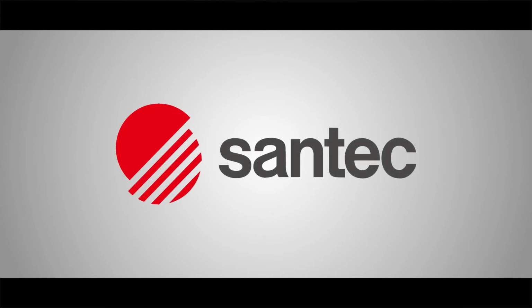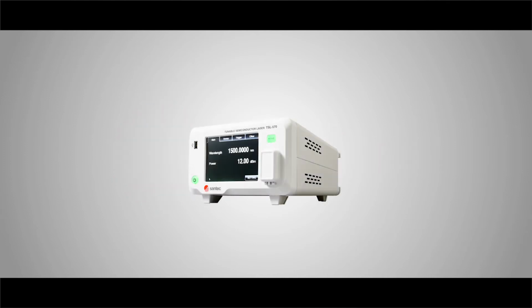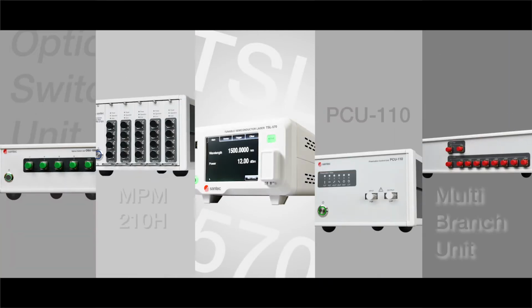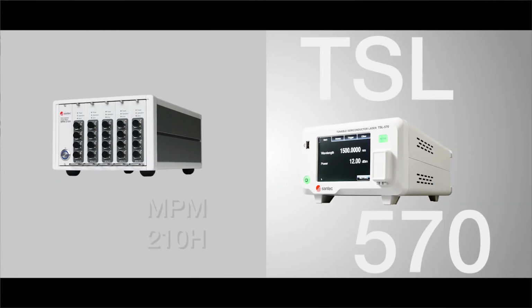Swept Test System, or STS, is Santec's photonic solution for testing and characterizing optical devices. Wavelength-dependent loss STS is designed to characterize insertion loss through passive optical components. It consists of a light source, the TSL 570, and a detector, the MPM 210.